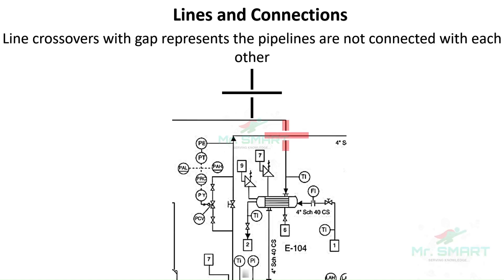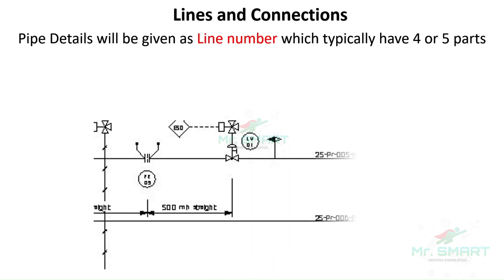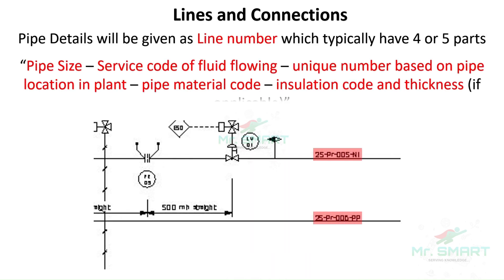Line crossovers, or lines with a gap between them, represent that the pipelines are not connected with each other. While making a physical connection, the pipes of these areas should not join with each other. All lines interpreting pipelines will be given a special alphanumeric code called a line number. A line number tells us the details about the piping connection to be made. Generally, the line number will have four or five parts and always starts with pipe size, followed by service code of the fluid flowing inside the pipe, a unique number ID given to the pipe based on its location, pipe material code, and finally insulation code and thickness if applicable.